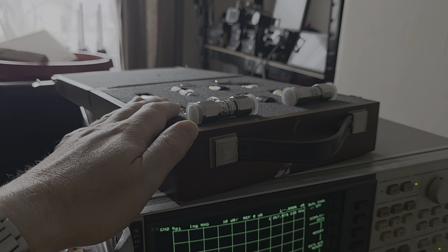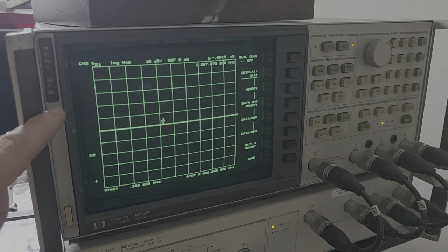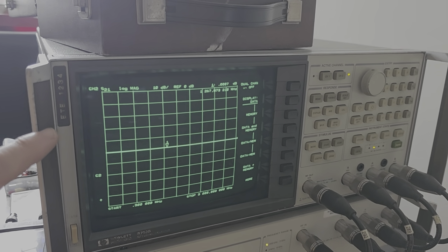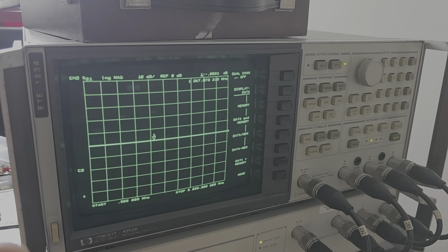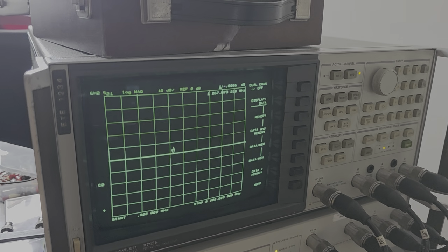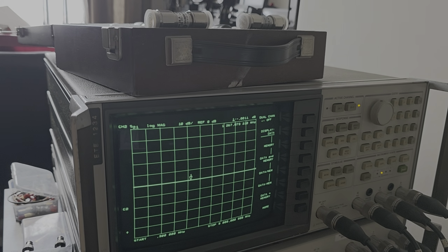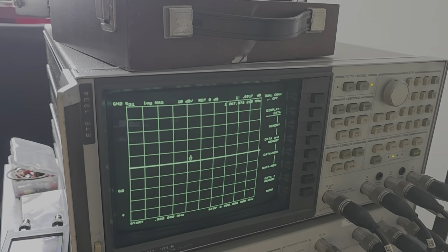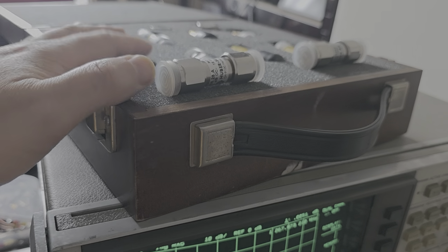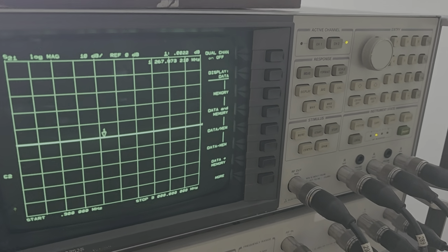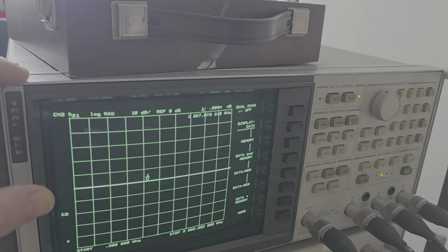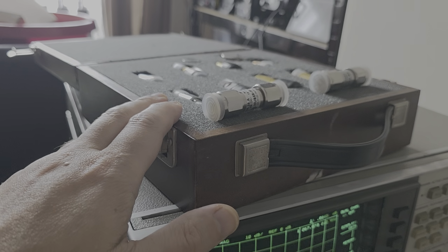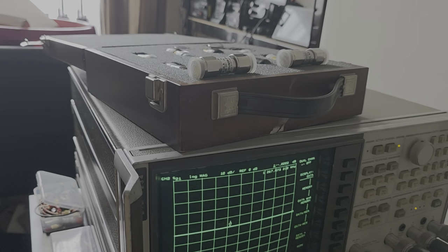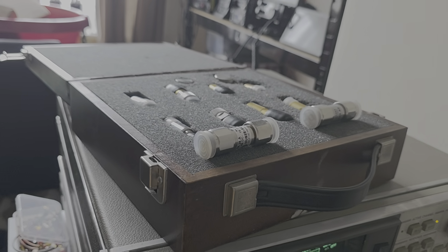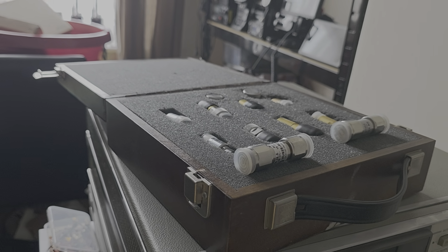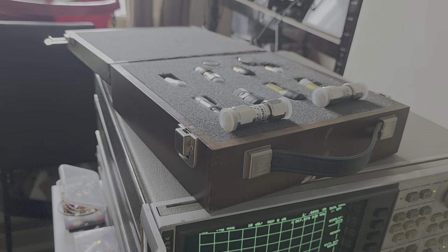If you buy one without documentation, it must be the one that is supported by the VNA in firmware, which is quite limited by firmware memory, so maybe it's not easy to find one that is in the firmware, or you can find one with the documentation and ingress the data as a user kit. But in that case, no problem, but obviously the kit with the calibration data will be more expensive than this one that doesn't have it. So one kit of this, even without documentation, can be 500, 600, even 1000, depending on the accessories that it has.